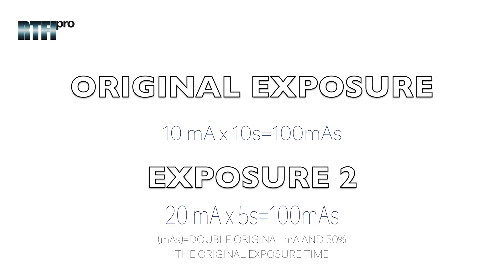If we double the milliampere, we would need to reduce the exposure time by 50% to get the same exposure. For example, if we have 20 MA and a 5-second exposure, we would still have a 100 MAS exposure. From this example, we can verify that the exposure is still 100 milliampere seconds as in the original exposure, due to doubling the milliampere and reducing the exposure time by half.